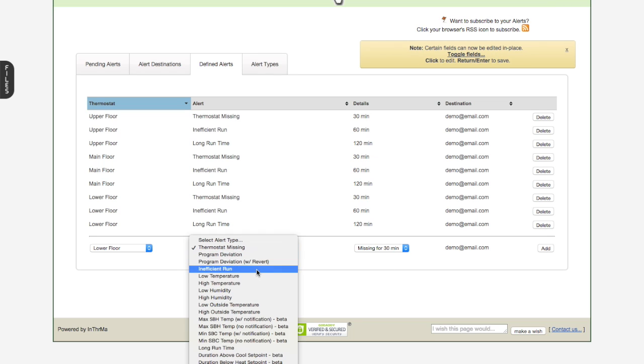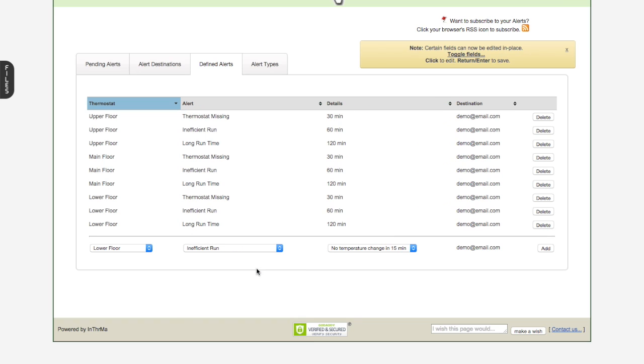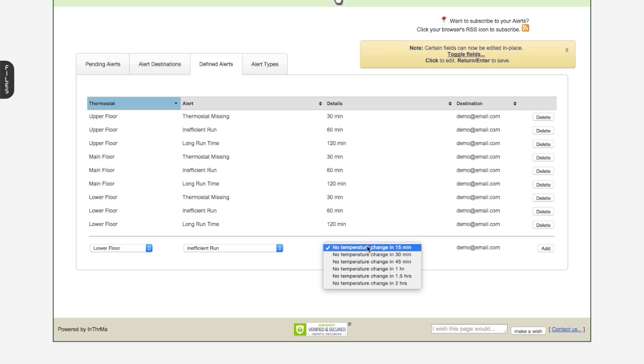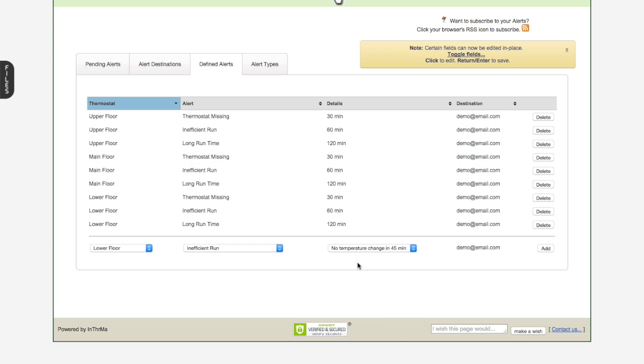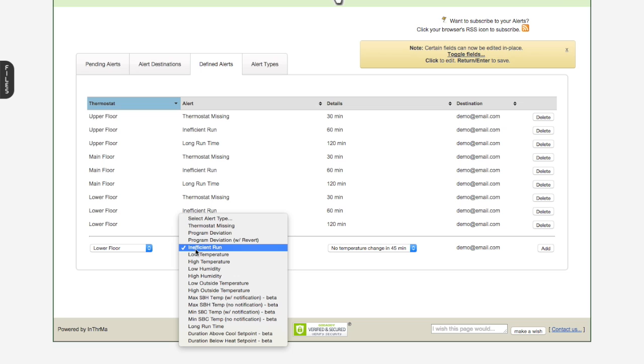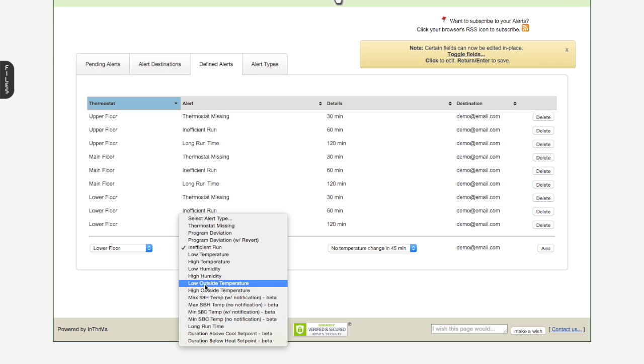The inefficient run, let's look at that one next. So the inefficient run says, if the air conditioning comes on, or if the heat comes on, and we don't detect a change in temperature within X number of minutes, in this case, whatever threshold makes sense for your system, and you might have to experiment a little bit to get the right threshold, let me know. So in this case, if the air conditioning comes on, and we don't see the temperature start to drop within 45 minutes, send the alert out to this destination.